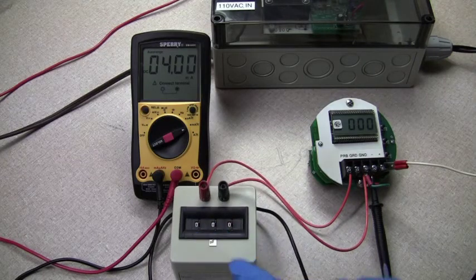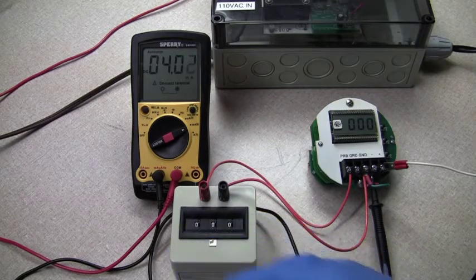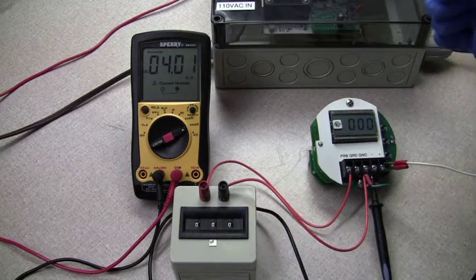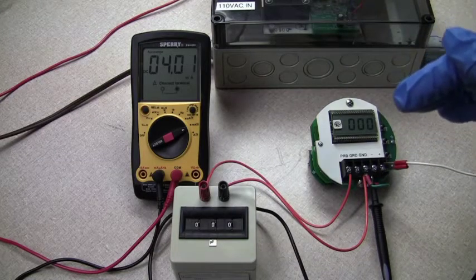I had already pre-calibrated this for low being zero pF and a hundred percent being 200 pF. So right now your liquid would be at the bottom of the probe or not even touching the probe.